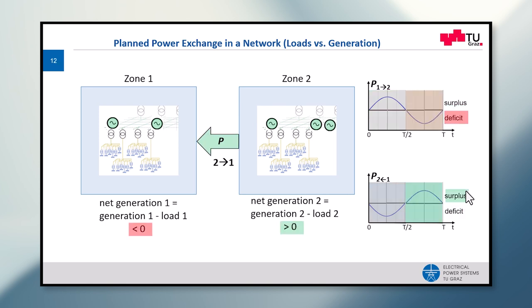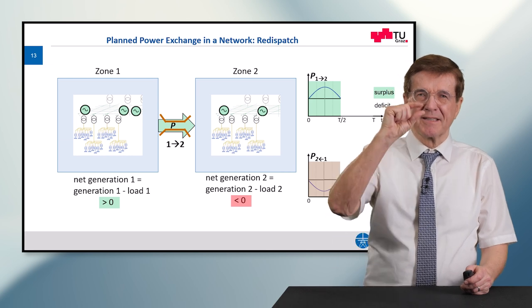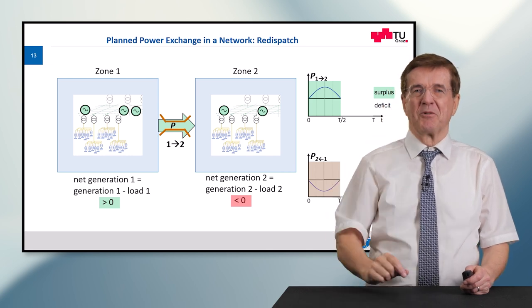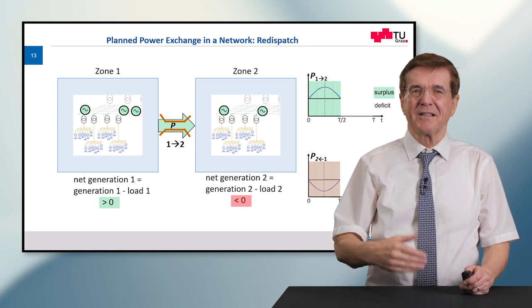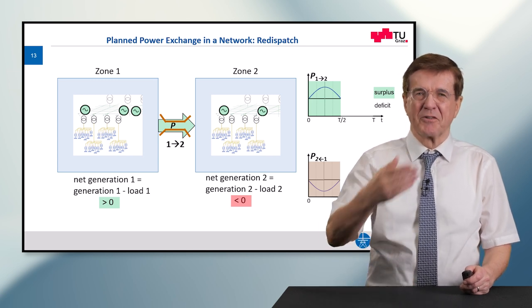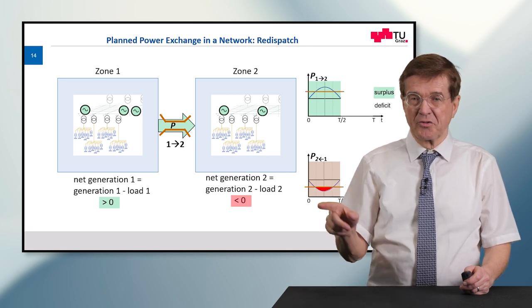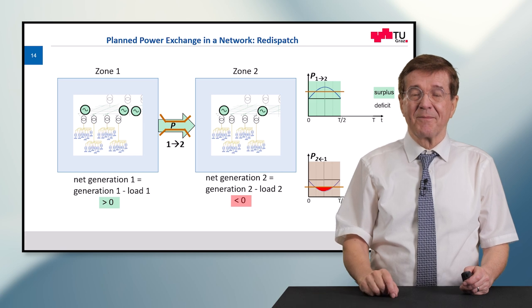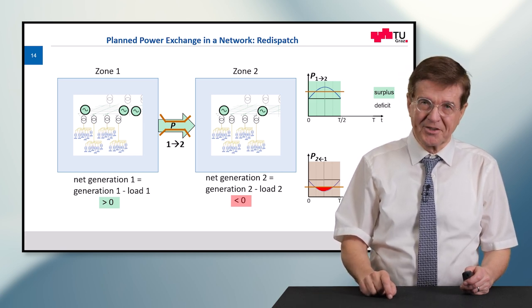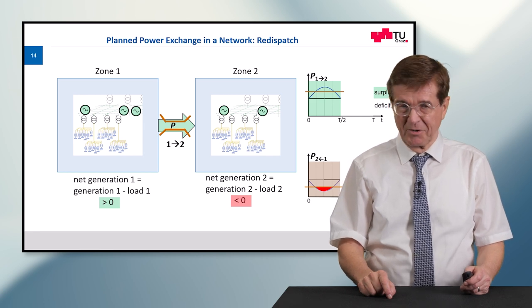Now let's assume that after a certain time this situation has turned around: there is a surplus in zone 2, a deficit in zone 1, and the power flow goes the other way. But what will happen if there is a limitation in the transfer of power? We call this a bottleneck. There is too little transport capacity for power and current, and this would mean a deficit in zone 2 which could develop into a crisis — requiring harsh measures like load shedding, which nobody wants.